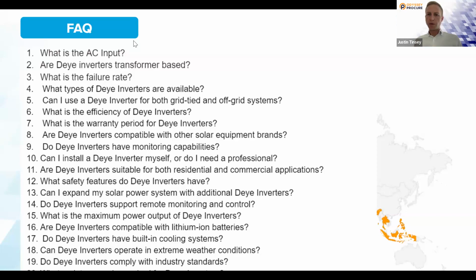Can it work only with solar panels without storage, like a grid-tie inverter? Yes, it can, obviously also without panels as backup. It totally depends on what you want to use it for. There are basic inverters for that — not every inverter works with solar panels to use the output energy directly. But for Deye inverters, I'll take that back; there are specific inverters for that. It doesn't work that way for Deye, but it can act as a bypass if you want — you connect to the grid, but not with solar panels. So not grid-tie.